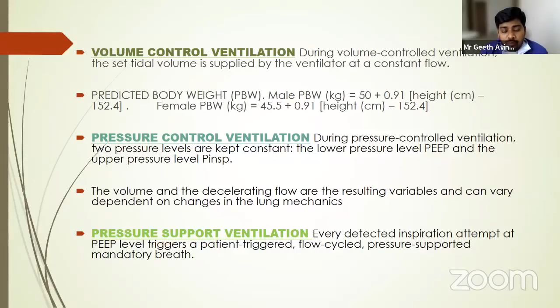And coming to pressure control ventilation, during pressure control ventilation, two pressure levels are kept constant. The lower pressure level is PEEP and the upper level pressure is the peak inspiratory pressure. The volume and the decelerating flow are the resulting variables and can vary depending on changes in the lung mechanics. Coming to pressure support ventilation, every detected inspiration attempt at PEEP level triggers a patient-triggered flow cycle, pressure support, mandatory breaths.